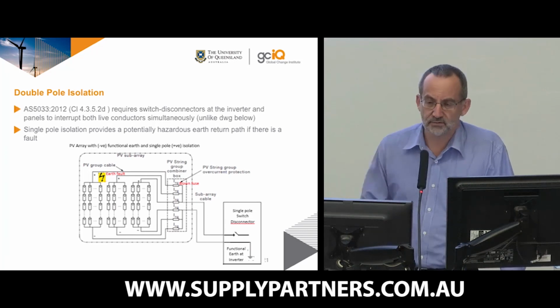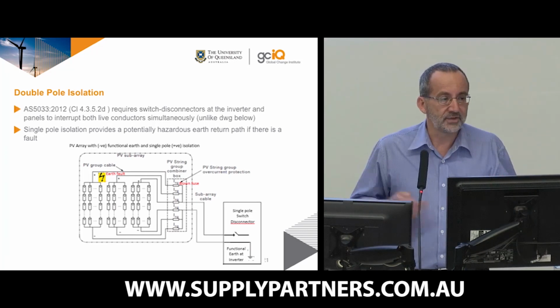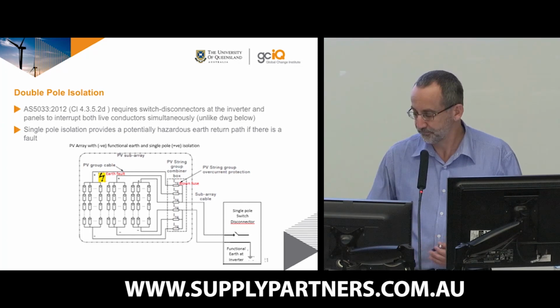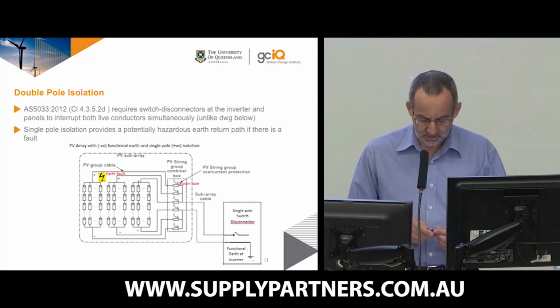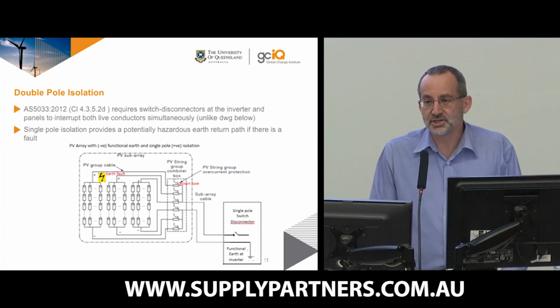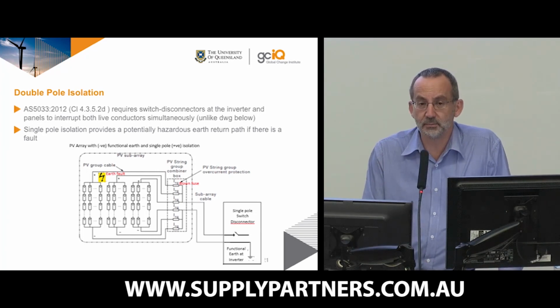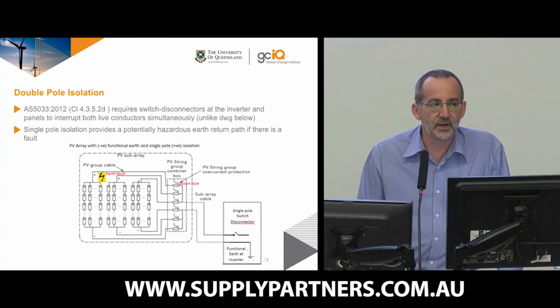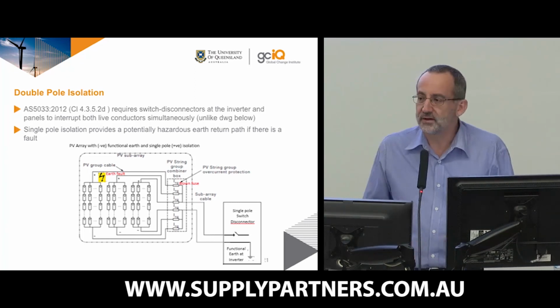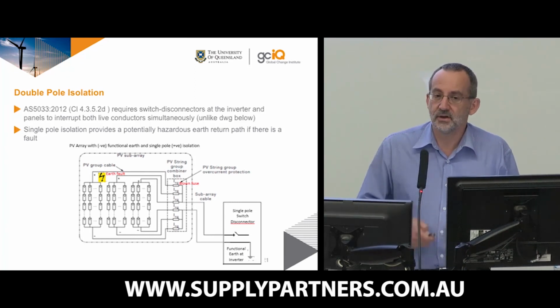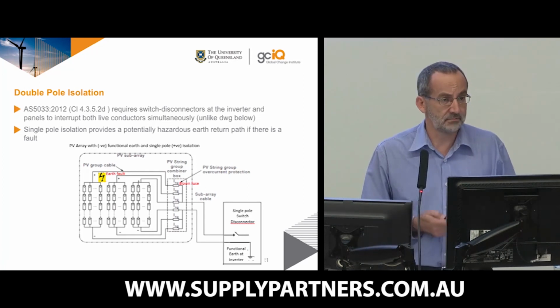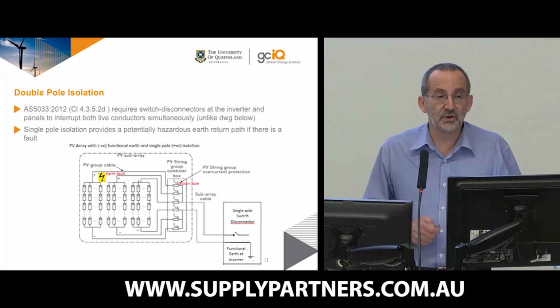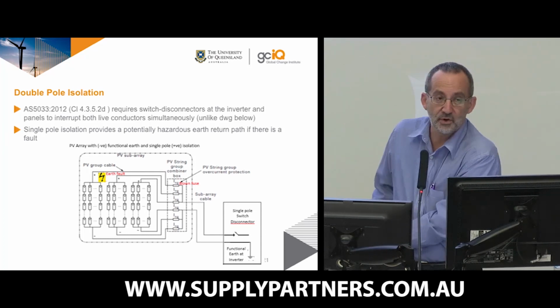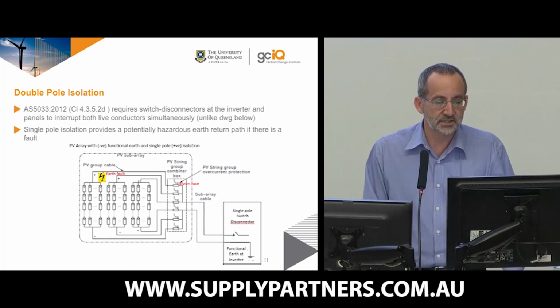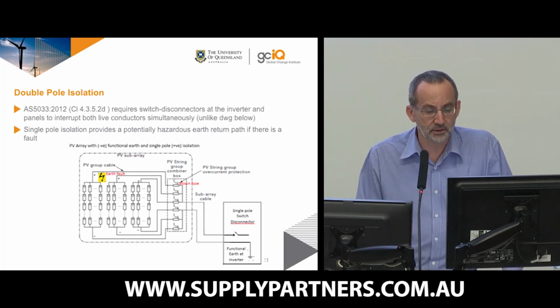So each morning the inverter looks at the positive and the negative. If there's any leakage to ground, it says, I'm not going to start off today. Another interesting thing is that some of these larger systems which won't have to comply with 5033 may only tend to use single pole isolators. Now, if you think about that, with the negative earthed, if you have a contactor frame, you've now got a potentially live frame if the earth isn't in place. At least if you've got double pole isolation, you've removed the earth return path on the negative, you've made it a little bit safer. So that was something we insisted upon.